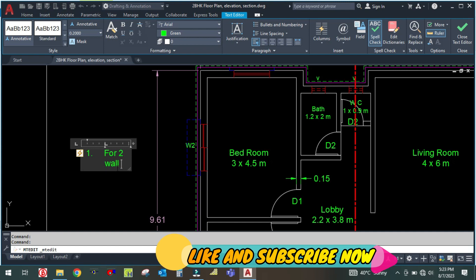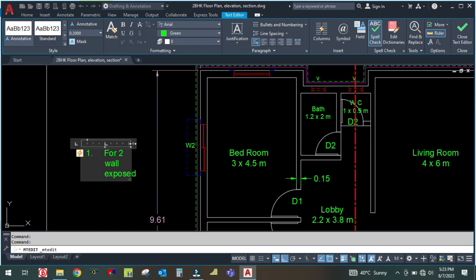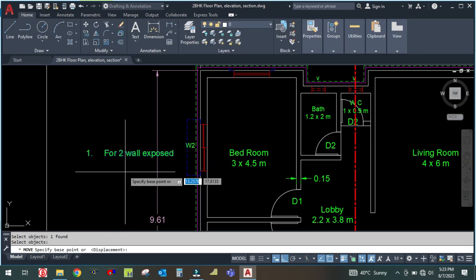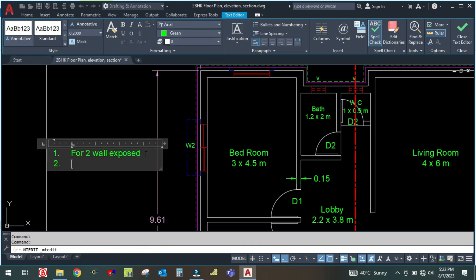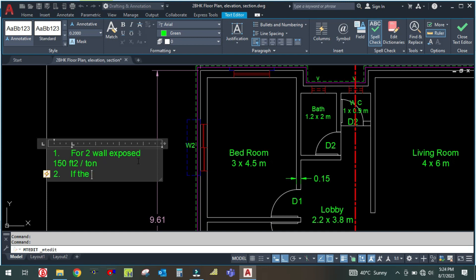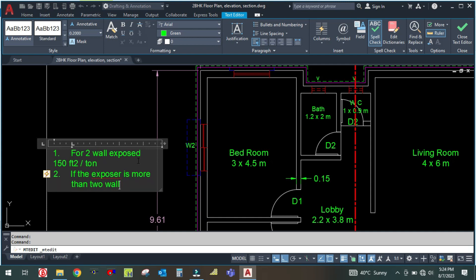For point number one — for two walls exposed — we are considering 150 square feet per ton. Second, if the exposure is more than two sides, then we are considering 100 square feet per ton.